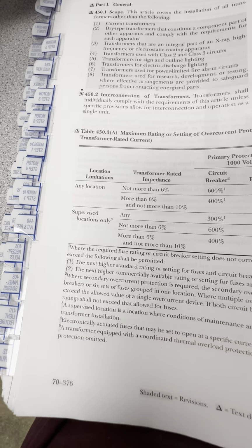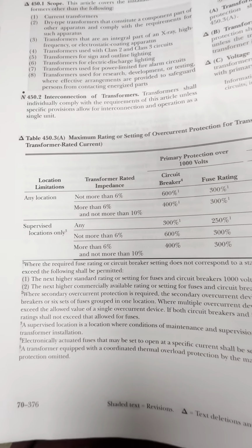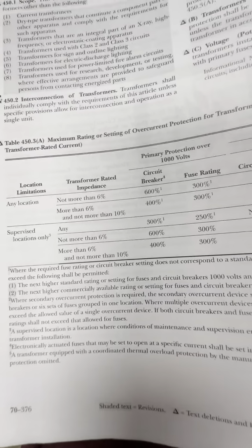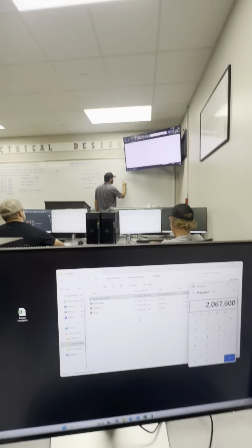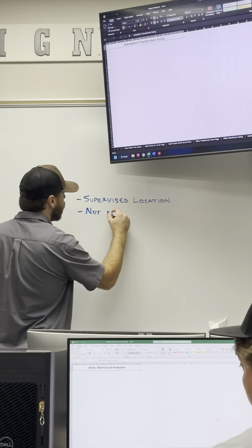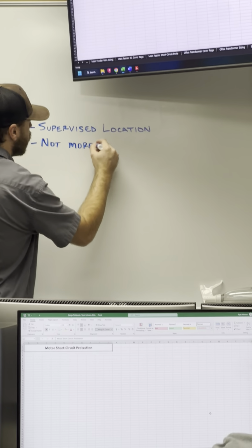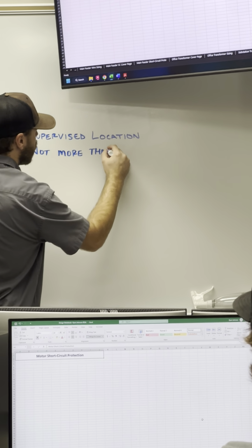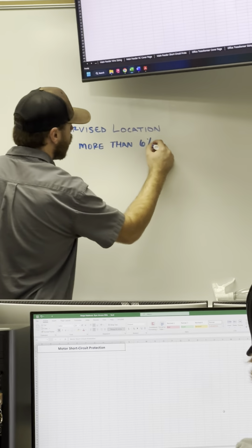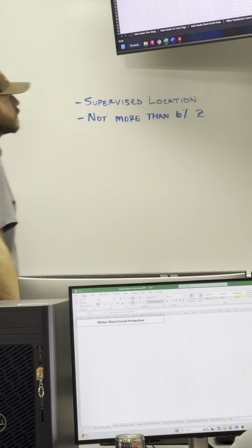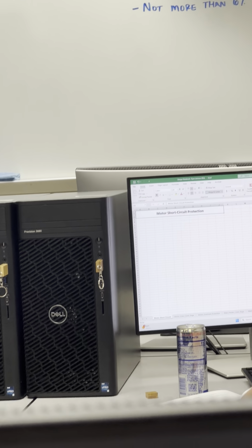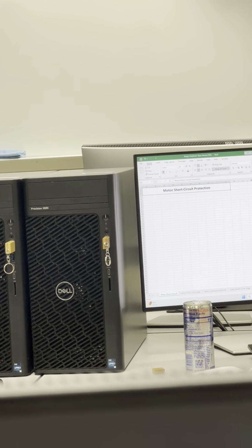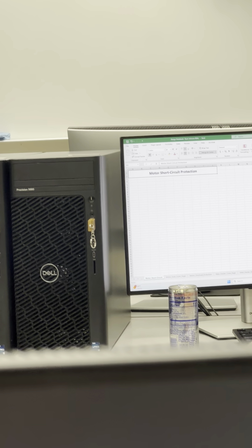Our next column, transformer rated impedance. We got 3 options there. We're going to fall in the not more than 6%. Not more than 6% impedance. So we were looking at that bottom half of the table. We still are, but now we're just looking at that one row of not more than 6%.